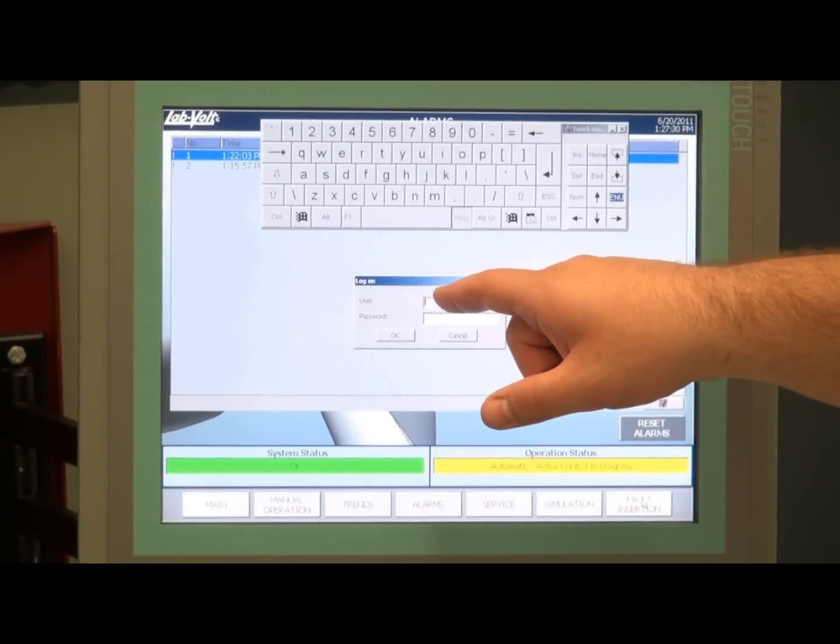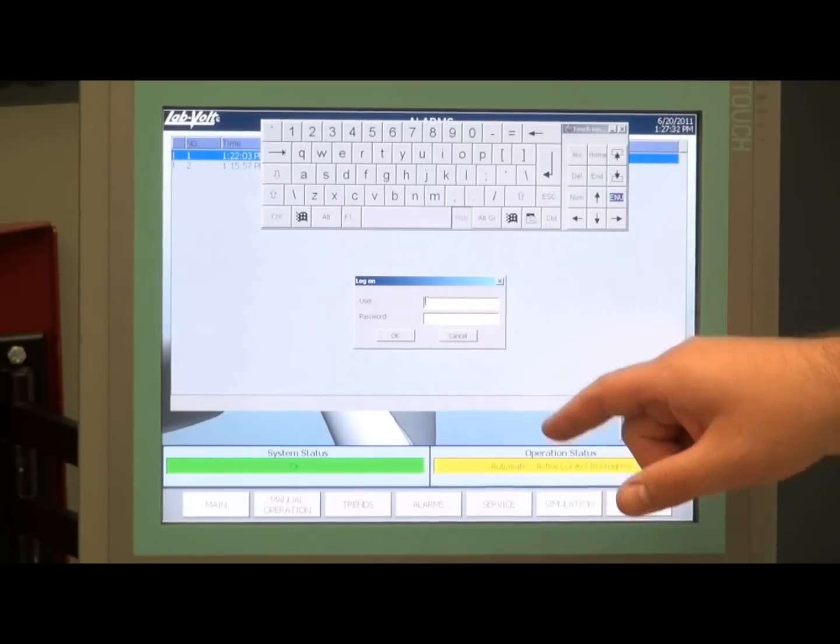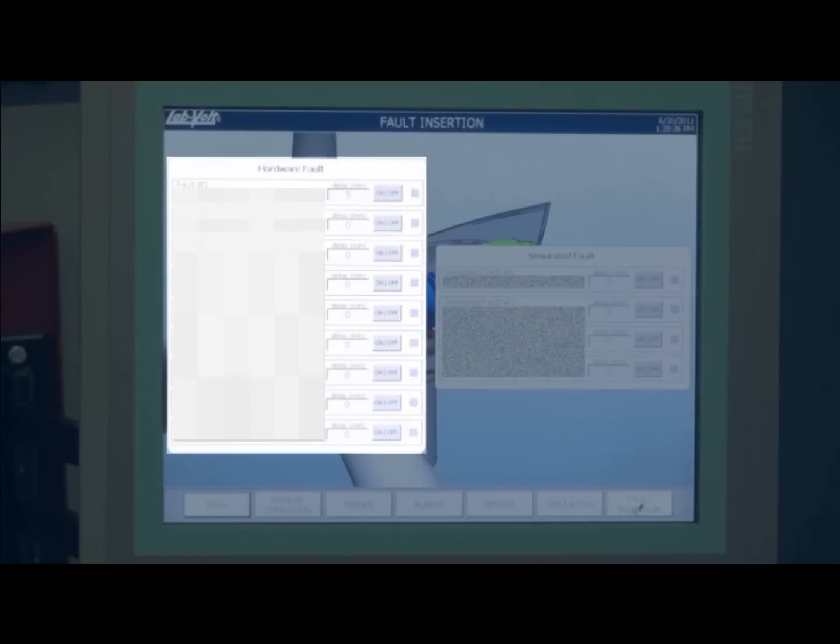A fault section is also available for teachers, where you have to enter a username and password, which are normally given by the teacher. Once the username and password have been entered, you can go to the fault insertion section, and you have a series of hardware faults, which are normally open contacts in the electrical panel, or simulated faults, like gearbox high temperature, or bad oil quality in the gearbox. The teacher can set a delay to when this fault will happen in the system, and then press the on-off button to activate that fault, and it will take place in the delay set by the teacher.